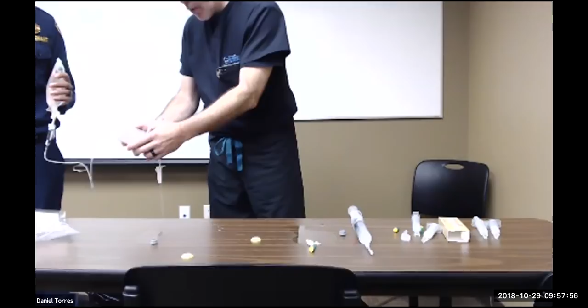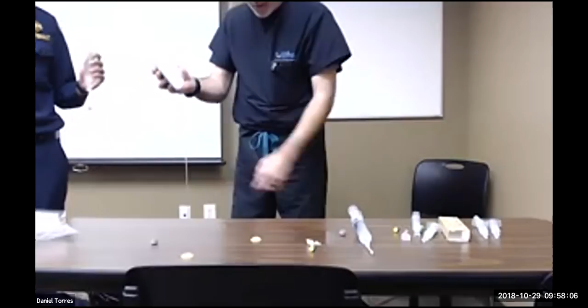And then from here, all we're gonna do is start new infusion and then dose calculation. That's gonna be in micrograms per milliliter. We're gonna type in 16. And then, okay, it's not a weight-based infusion. We're going to run this in micrograms per minute. And we'll say we're going to start at 50, so our dose rate, 50 mics per minute. And then our volume to be infused is going to be 250. And that's going to give us an hour and 20 minutes out of that one pre-mixed bag. It's going to ask us to confirm. So we confirm, and then we start the infusion. So now it's running 50 mics per minute.